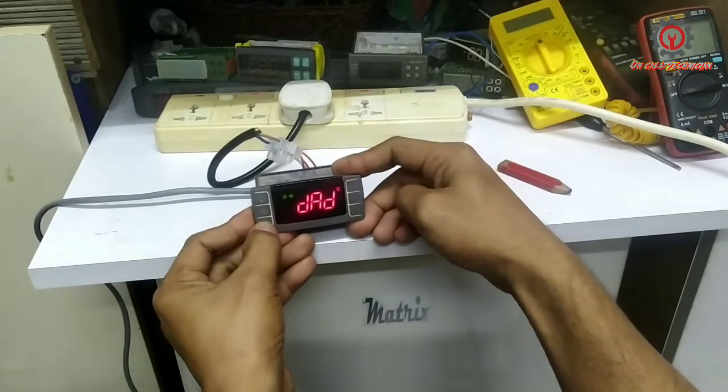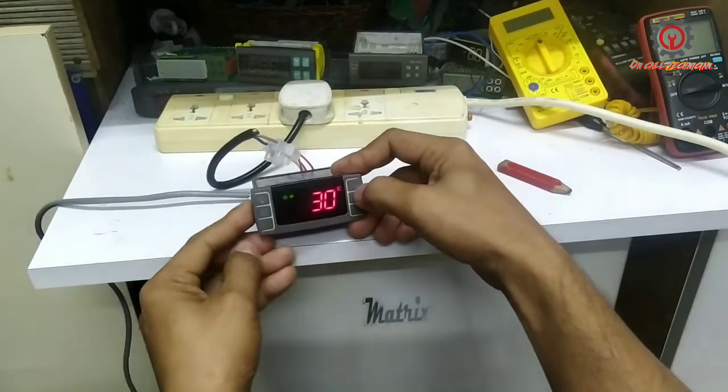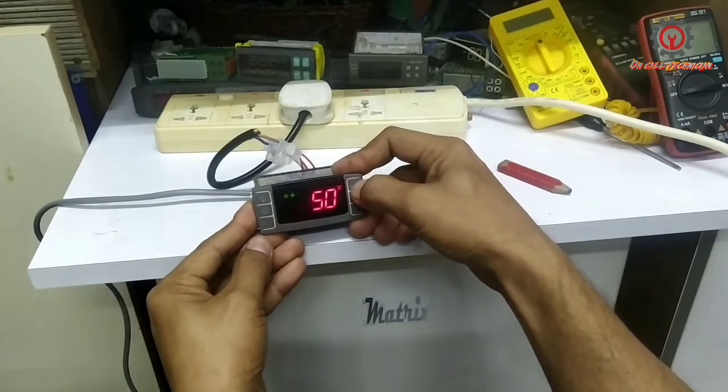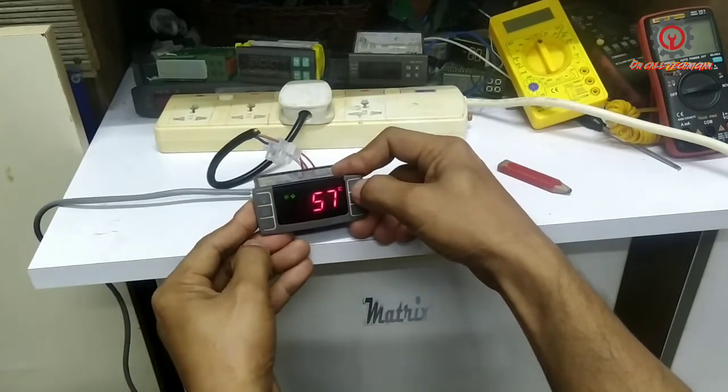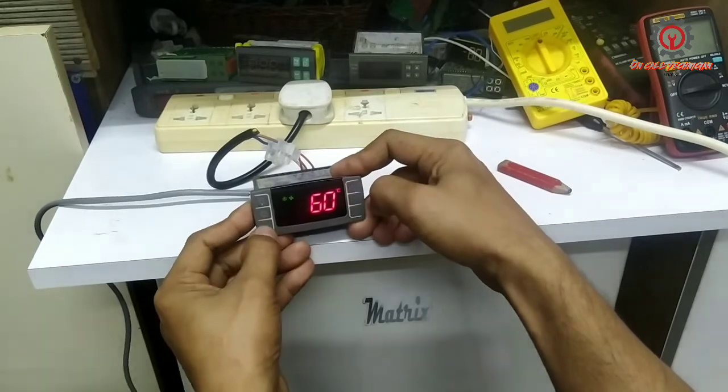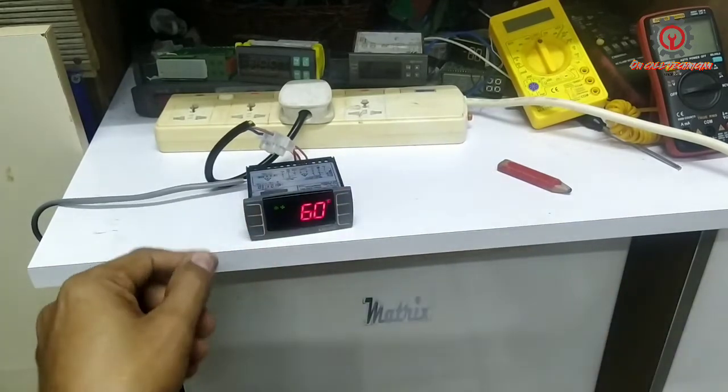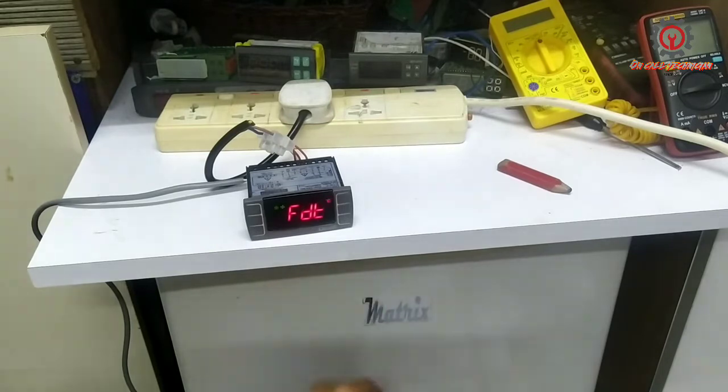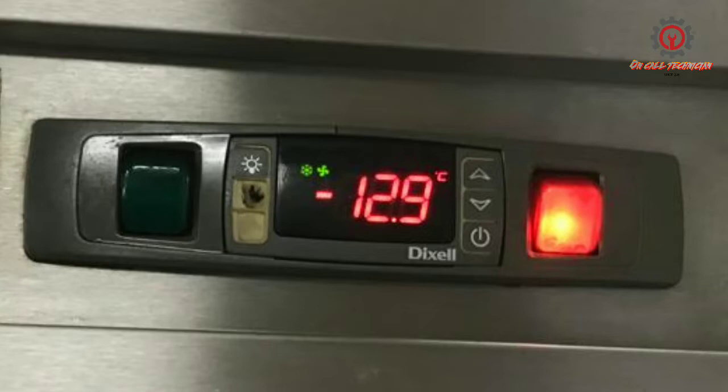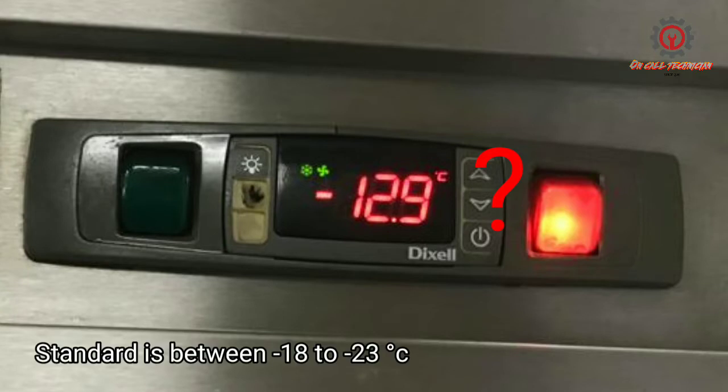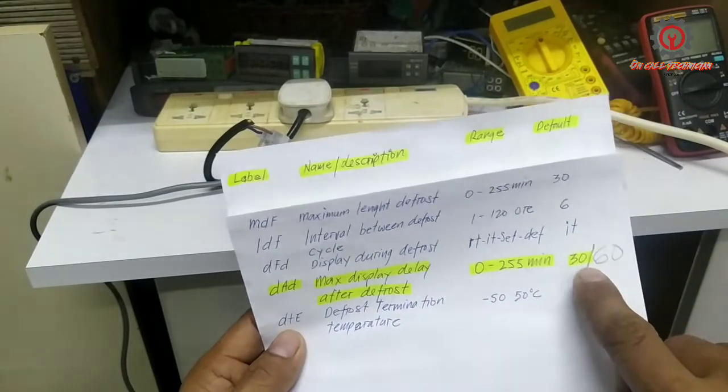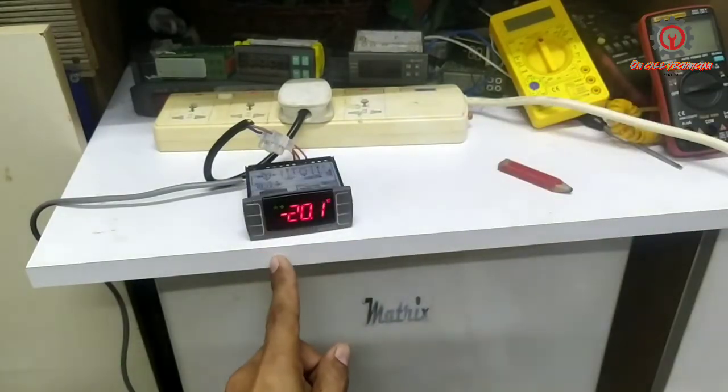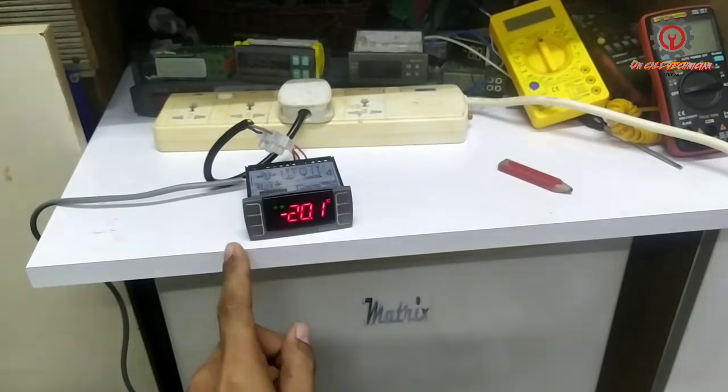The DAD - press SET. 30 minutes, we're going to change that to either 50 or 60, which is one hour, so that the people near this unit will not get alarmed if they saw that the cabinet temperature is not in standard temperature because of the defrost. We set it to 60 minutes, and by that time they will not get alarmed and will not call the attention of the technician.